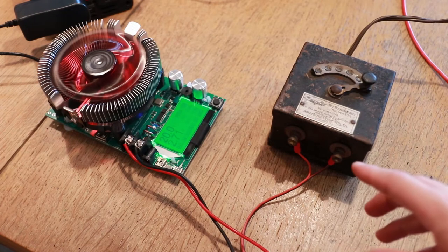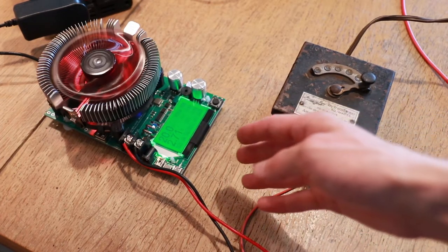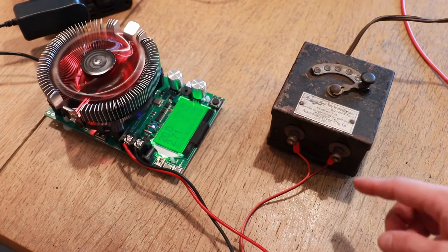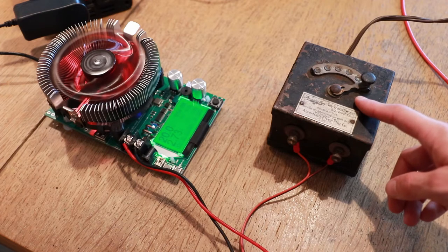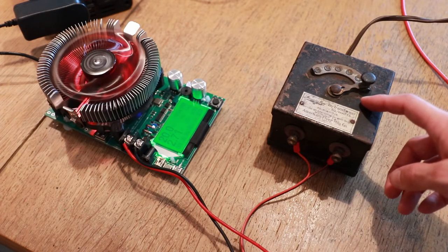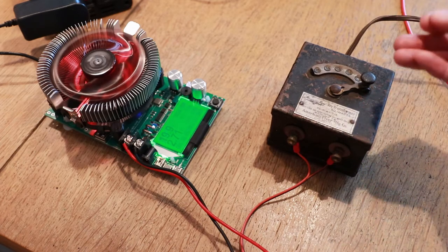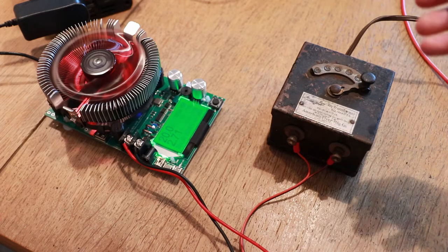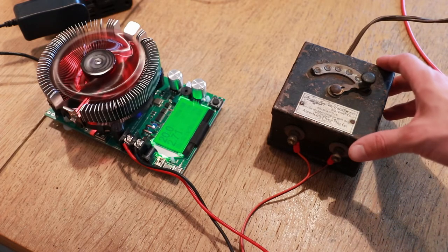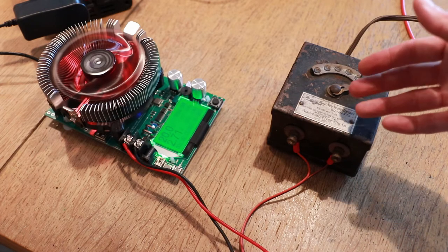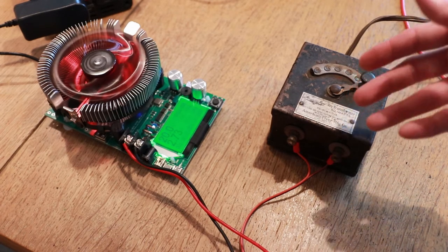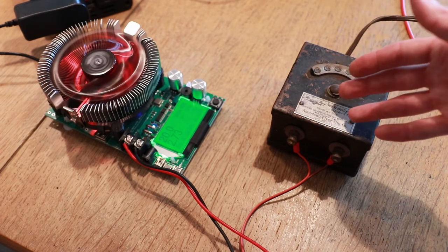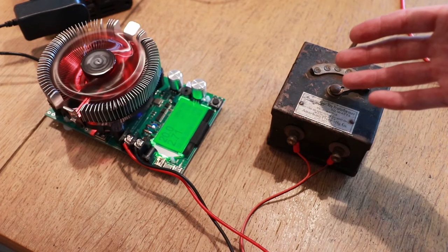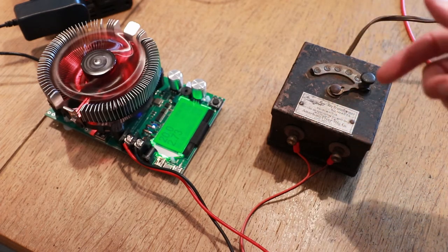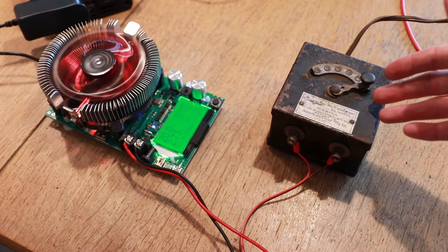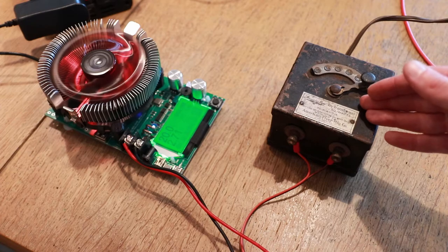In case you're wondering why increasing frequency and voltage leads to higher power transfer: this transformer was primarily limited in supply voltage by the saturation current it would draw as voltage increased. The higher the applied voltage for a given frequency, the more current it takes to magnetize the iron core, and beyond a certain point the core can't be magnetized further. This is saturation - the transformer stops acting like an inductor and starts acting like a short circuit or low-value resistor. That's actually what was happening at 60 Hz, even at just 120 volts.